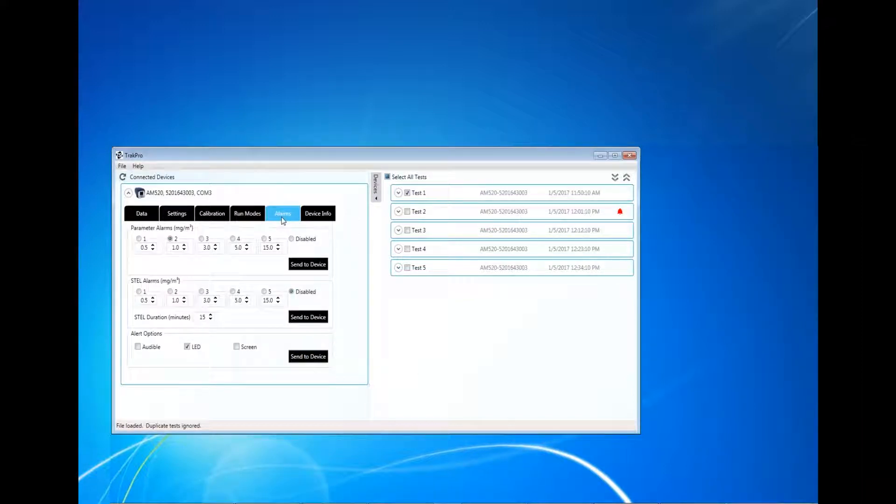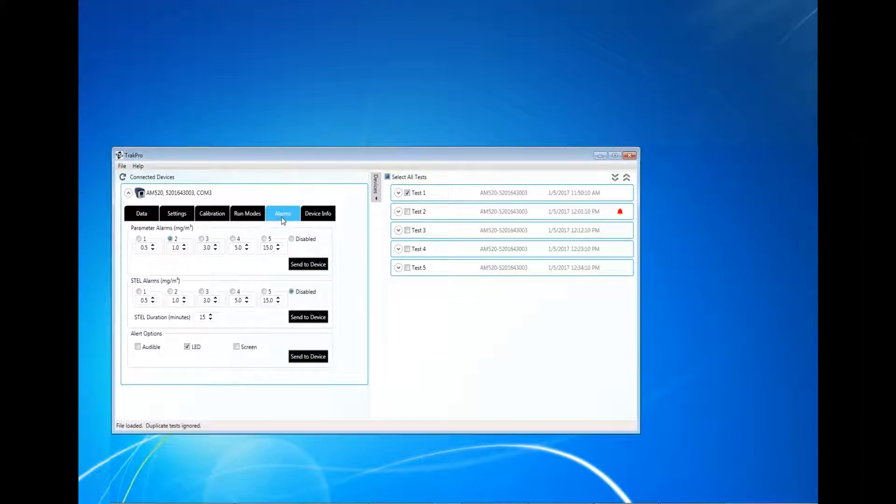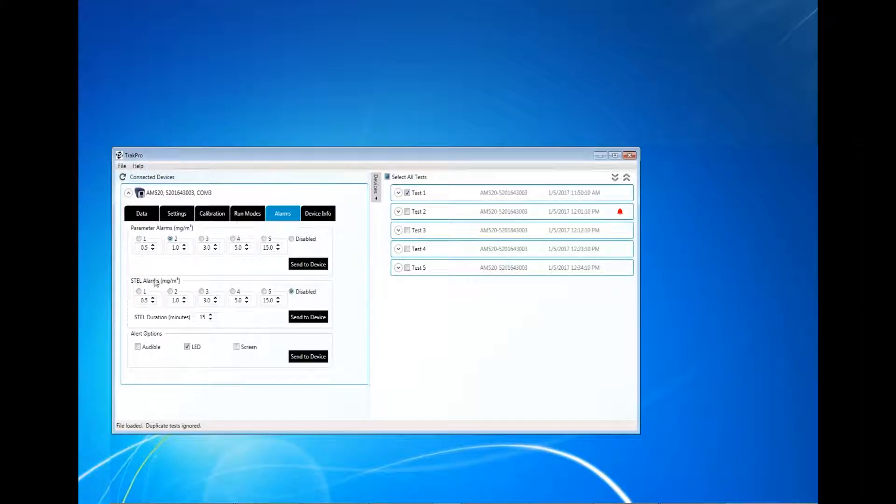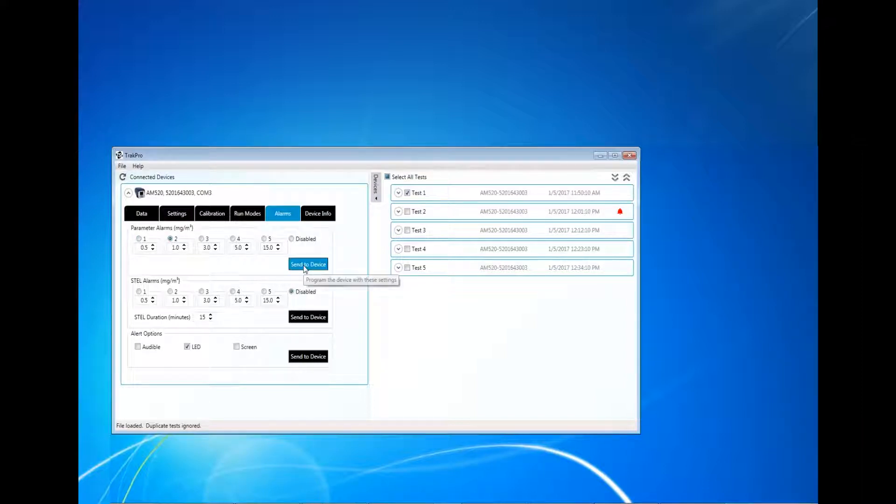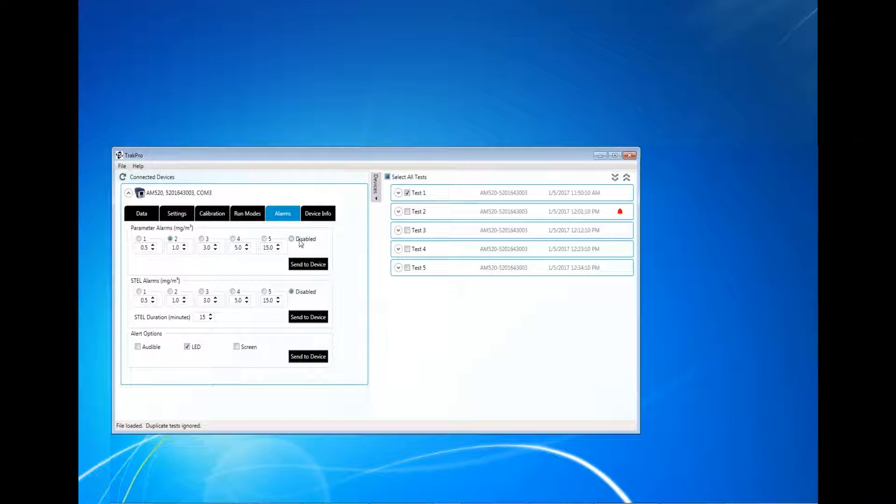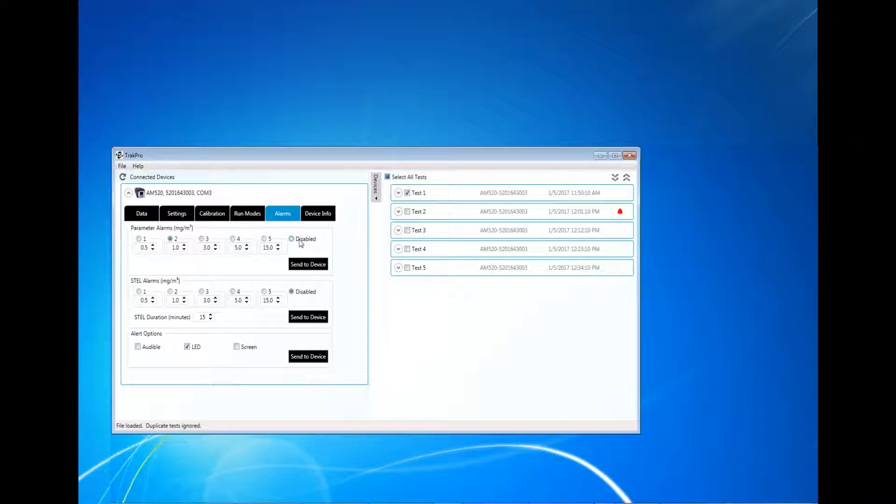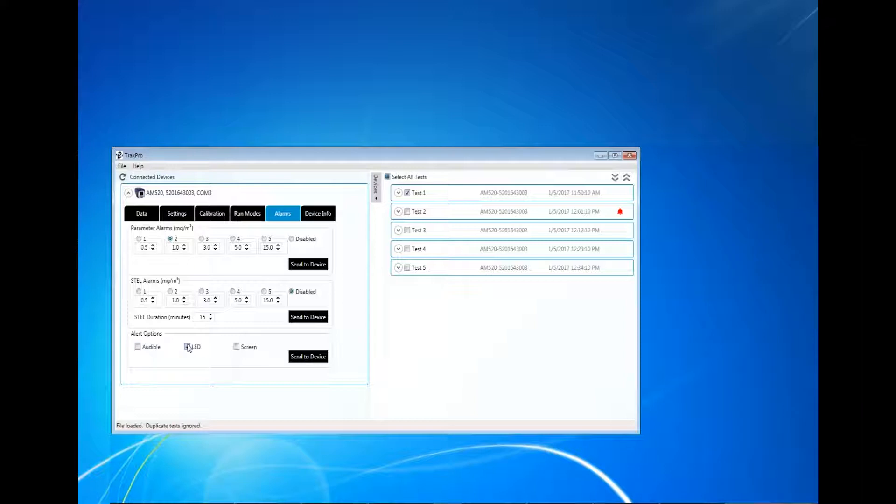The Alarms tab allows the user to configure the parameter alarms, also referred to as General Alarm in the User Guide, STEL Alarms, and Alert Options. Click one of the five alarms and send to device will enable that specific alarm. Click Disabled if you prefer not to use an alarm during monitoring. Keep in mind, the parameter and STEL alarm values can only be adjusted using the TrakPro 5 software. The actual values cannot be adjusted using the AM520 keypad and functions, but the user can pick which alarm should be enabled using the AM520 keypad.